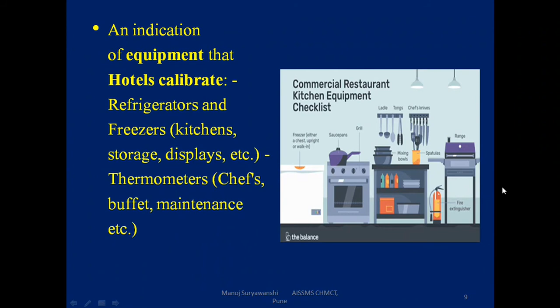Importance of calibration. Now we should know why it is important and how we can utilize it in the proper way. The main reasons for calibration are to ensure the reliability of the instrument, that it can be trusted. Like I have mentioned, if the equipment is faulty or is not showing accurate temperature or measurement, we might make mistakes in the process of the systems or the things which are required to go in a proper flow. So that is why calibration should be accurate. It should not show any kind of invalid value. Another reason is to determine the accuracy of the instrument and to ensure the readings are consistent with other measurements.